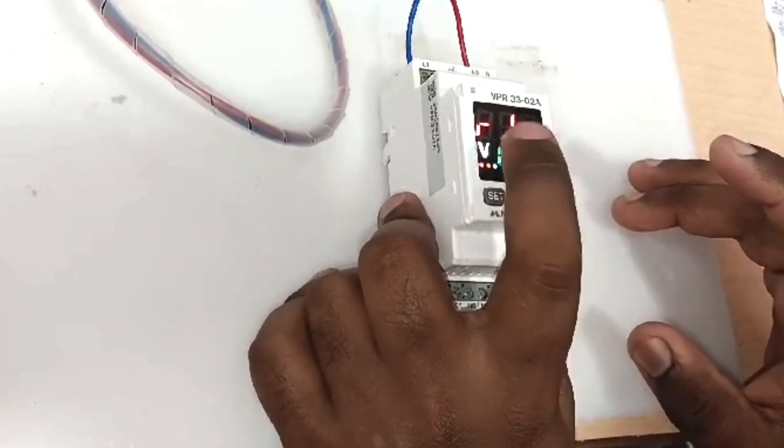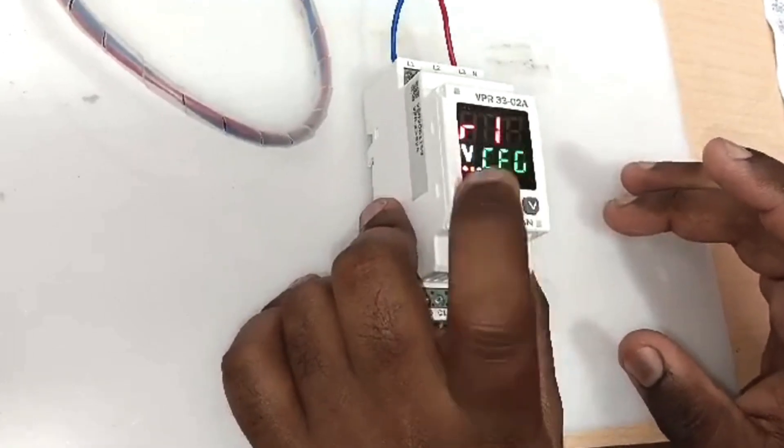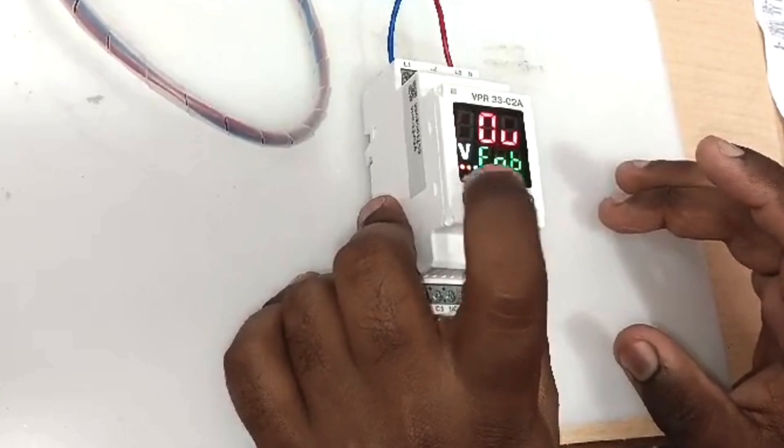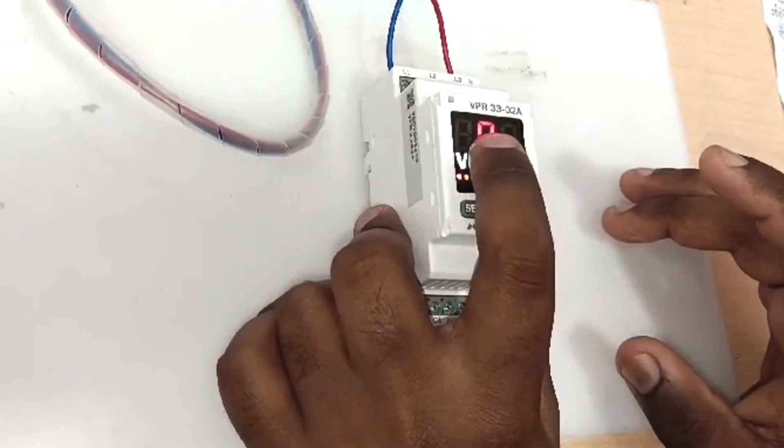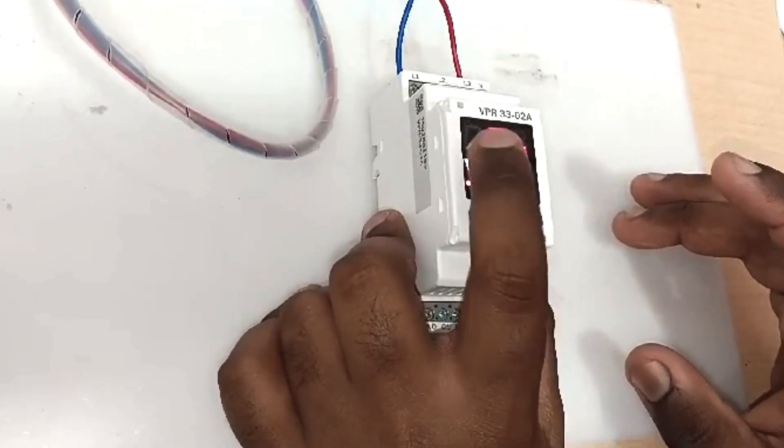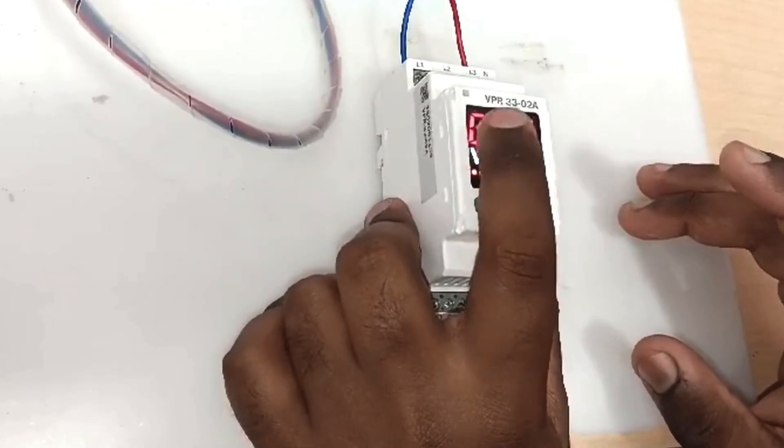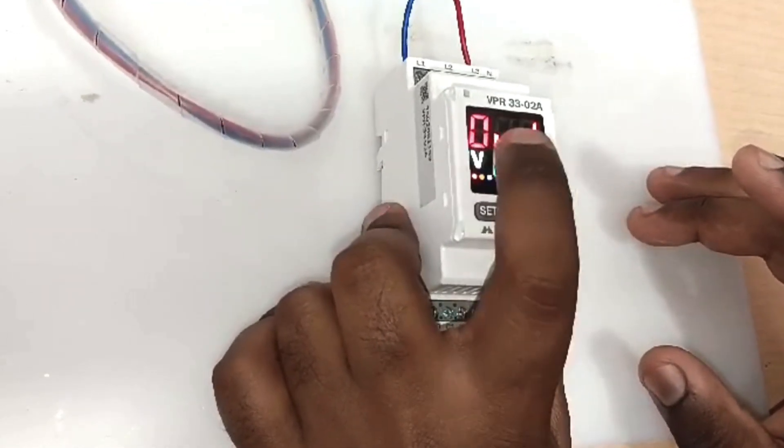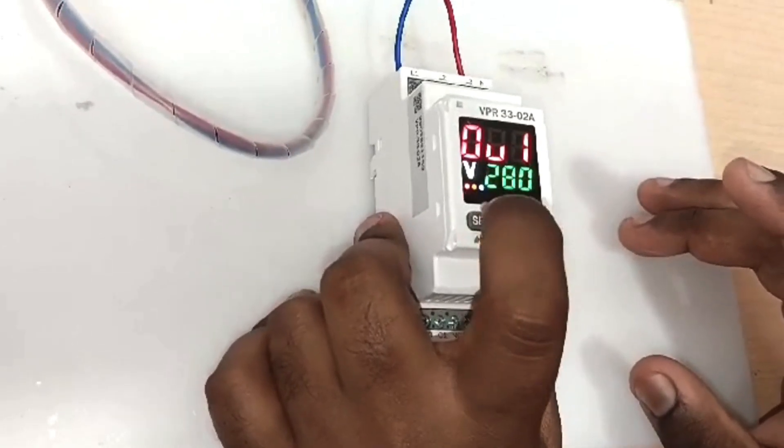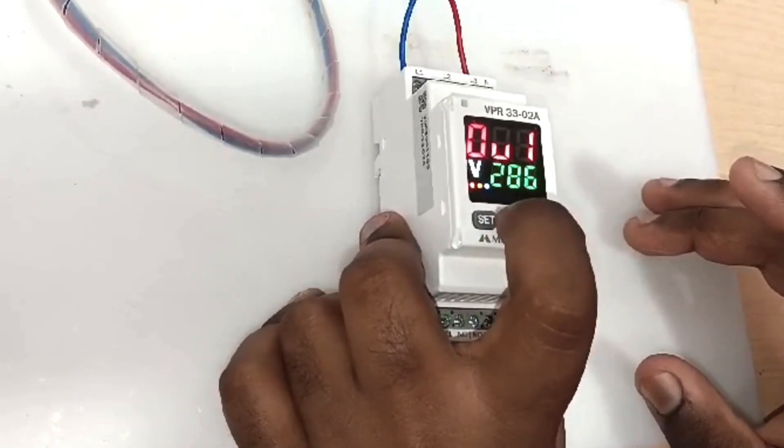Then press set button and next you get voltage configuration. You have to use up arrow and go to voltage relay one and press set button. This is over voltage. Now we have kept over voltage as enabled. Here you can configure the value of over voltage. Let's keep it at 240V. Now I have kept it to 240.